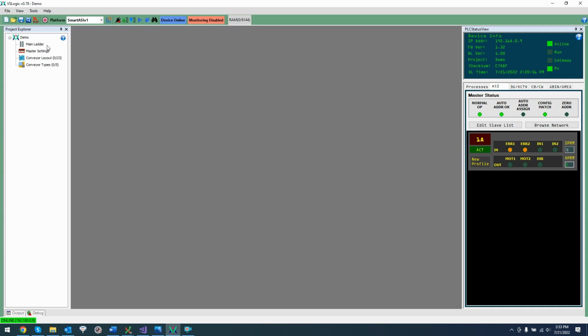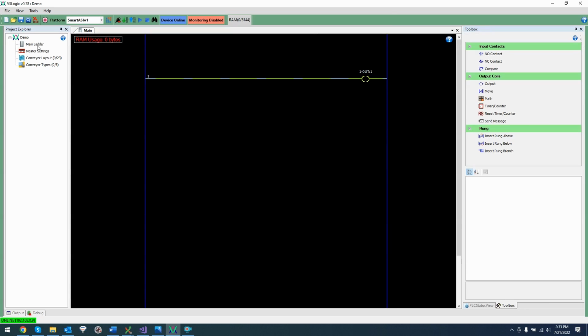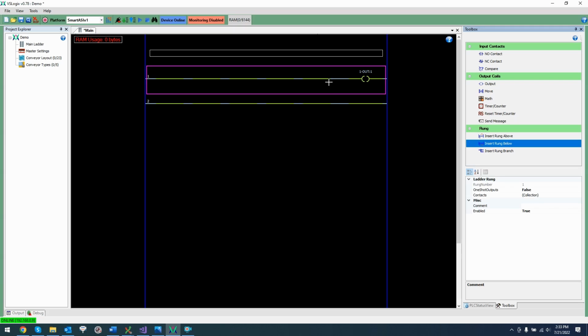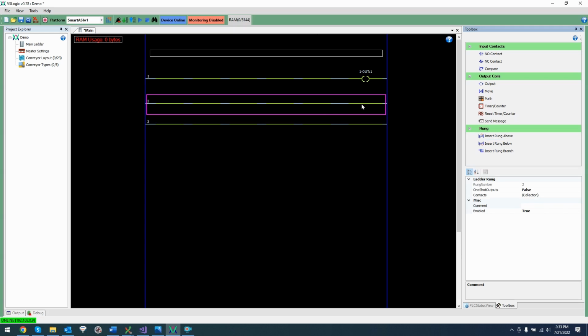If the speed of the roller needs to change during runtime, we can accomplish this inside our ladder by using the file type O_param. I'm going to toggle the parameter between 0 and 2 roughly once a second. I'm going to set up 2 move commands on different rungs to set the O_param value.